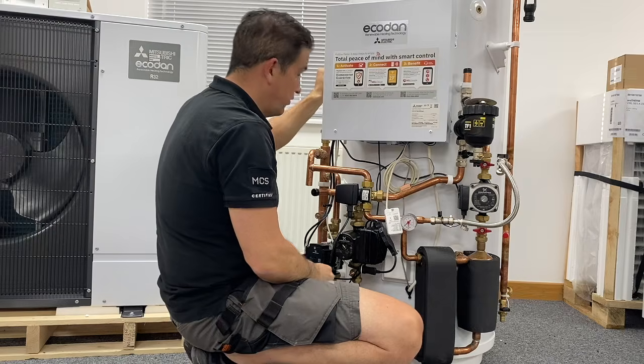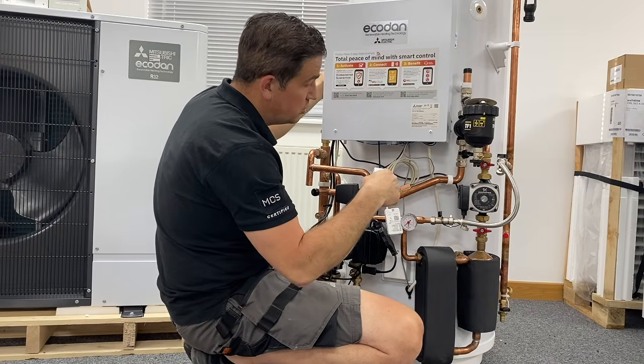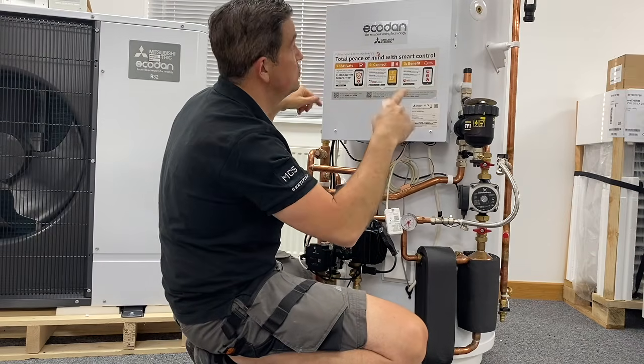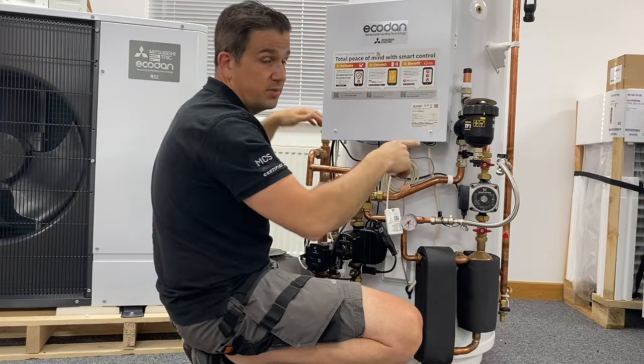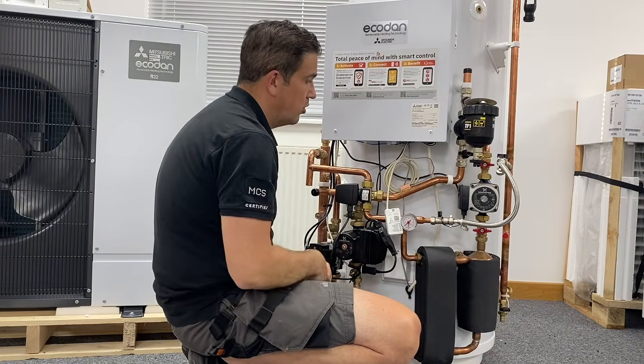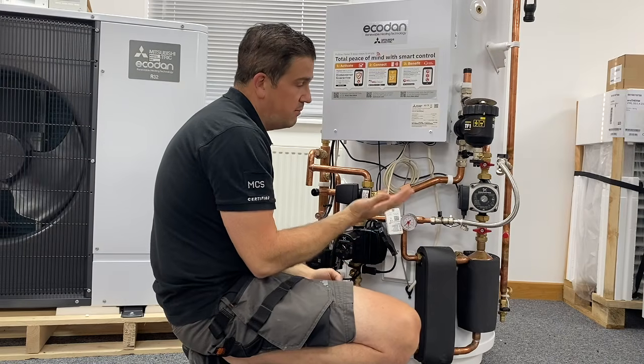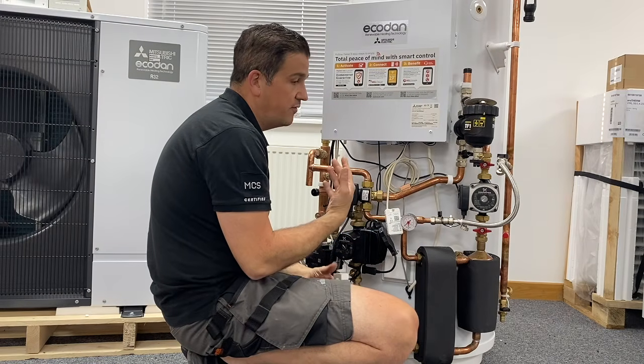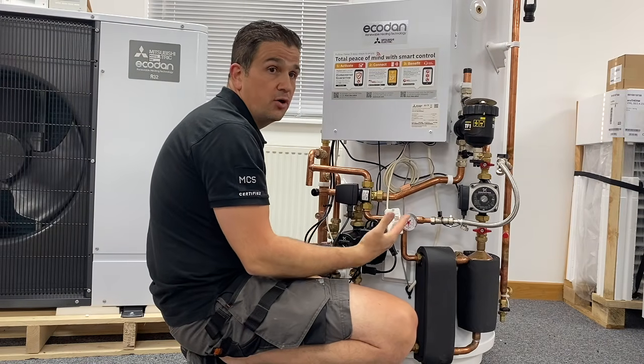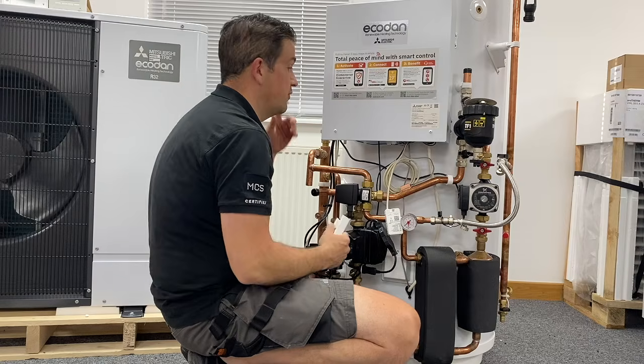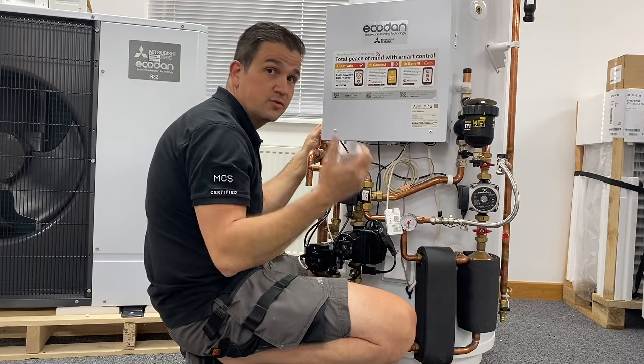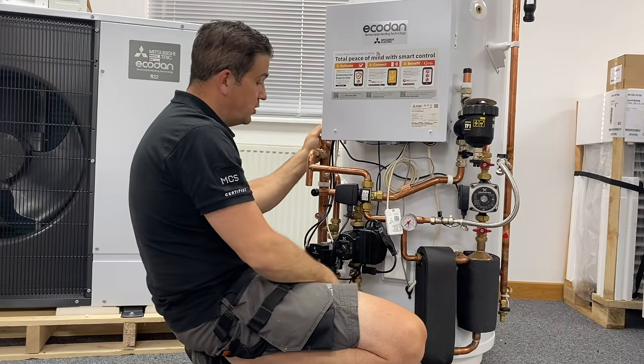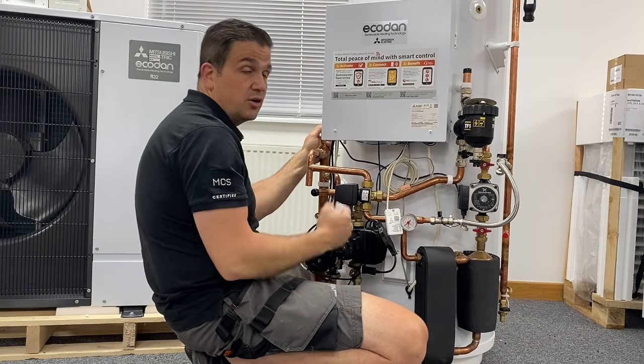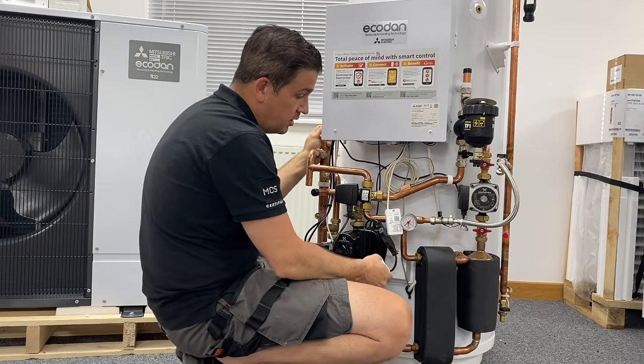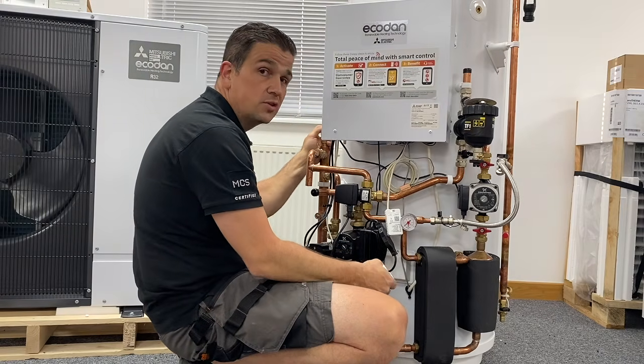On the newer ones, they've actually got two thermistors, one higher and one slightly lower. You've got different controls, so you can have a normal hot water mode, where it reads off one thermostat and gives you hot water at the set temperature, or you can have a larger capacity and add that into your cylinder. So you've got quite a high hot water demand at home.